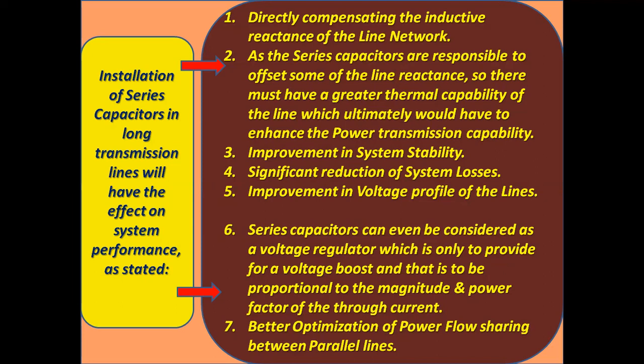Number 2, as the series capacitors offset some of the line reactance, there is a greater thermal capability of the line, which ultimately enhances the power transmission capability. Number 3, improvement in system stability. Number 4, significant reduction of system losses. Number 5, improvement in voltage profile of the lines.